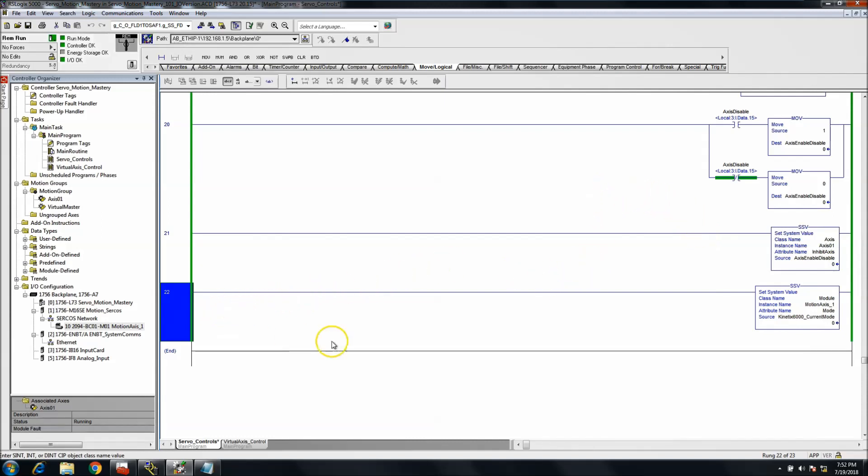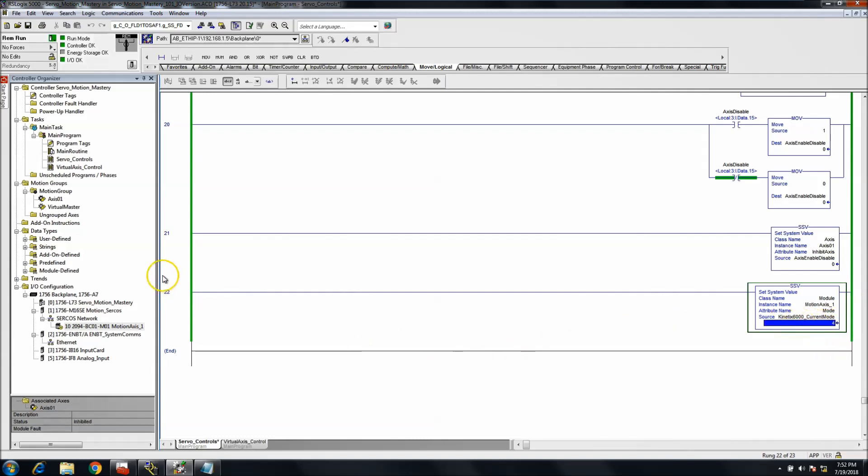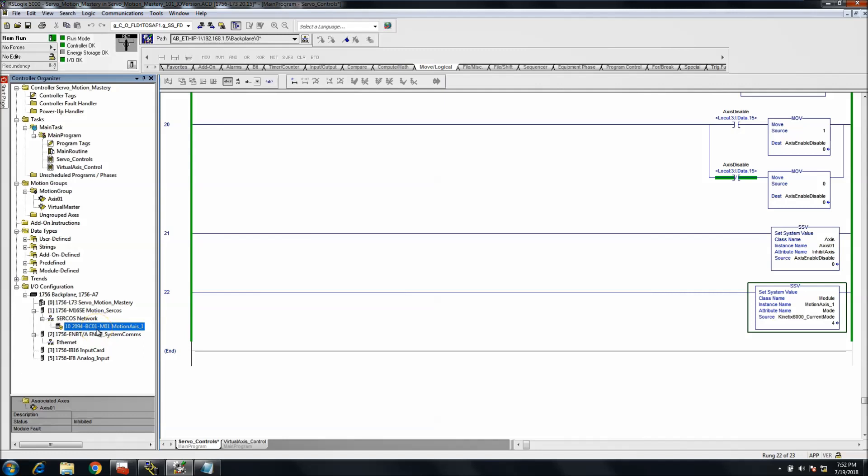So what we can do is I'll show you, you can just merely just change this to a four and now we have inhibited our Kinetix 6000 drive. This is our servo drive, right? This is the actual node that we're inhibiting this time, not the axis itself, but we're actually inhibiting the controller, the drive, the servo drive itself.